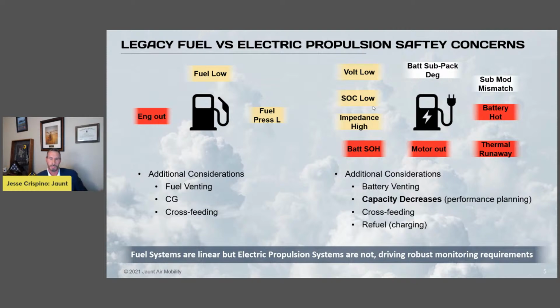If you pull too much power with a high impedance, as the state of charge droops and that impedance is creeping up, you might drop the voltage, a transient voltage drop that could theoretically drop a motor offline or cause permanent cell damage. And that impedance changes as the state of health of that battery changes. We talked about it. These batteries will age.